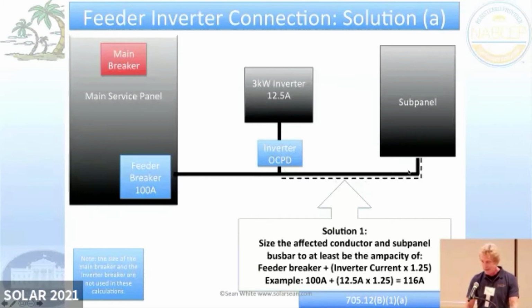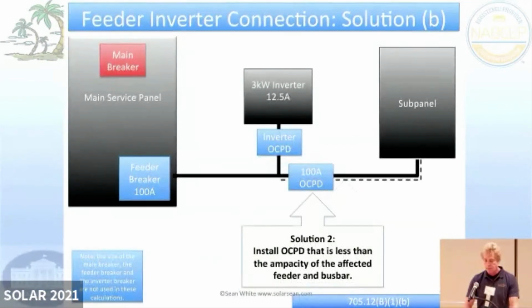But if it can't, if it's a 100 amp wire right there, here's another solution. We put an overcurrent protection device here. We could put one right here, and that works really nicely. But it's also kind of awkward, because this feeder was already there, and then I'm going to go stick this 100 amp overcurrent protection device in. So that's kind of inconvenient. And sometimes a sub panel might already have a 100 amp breaker in it.